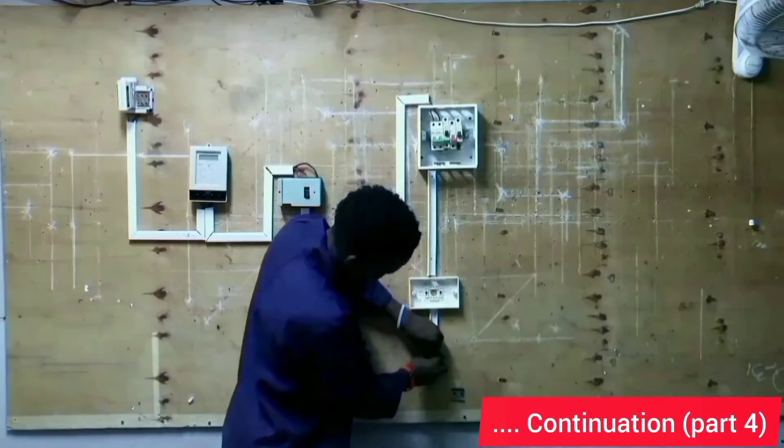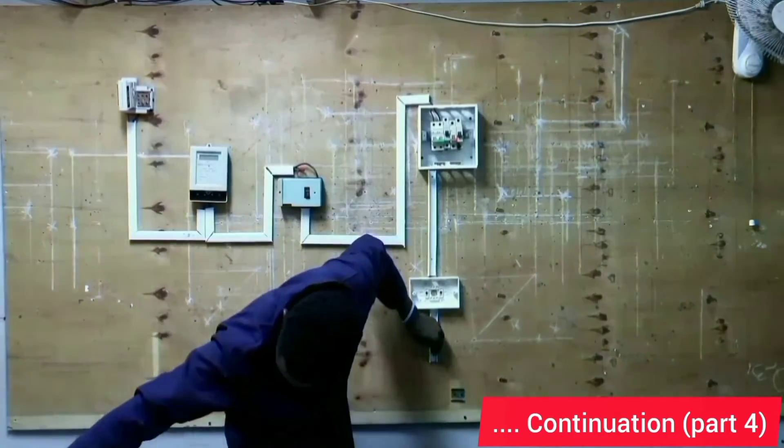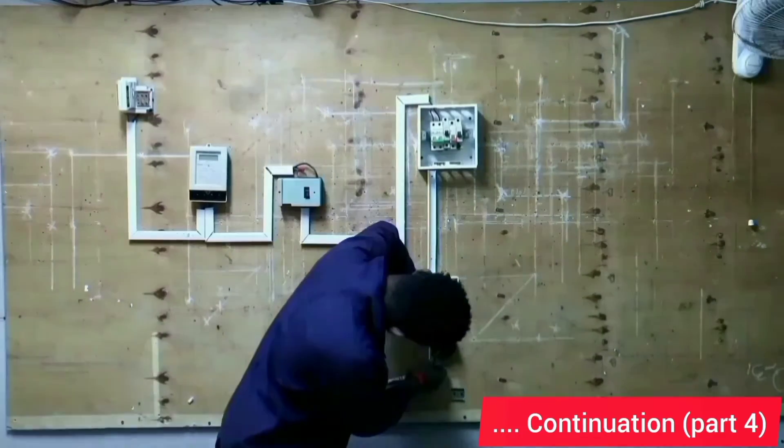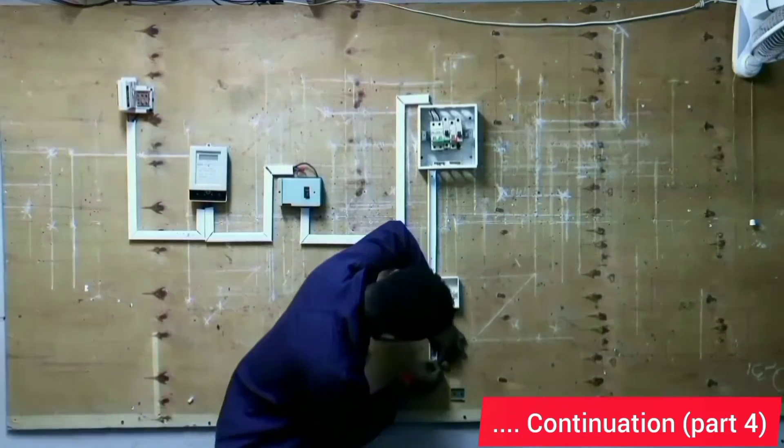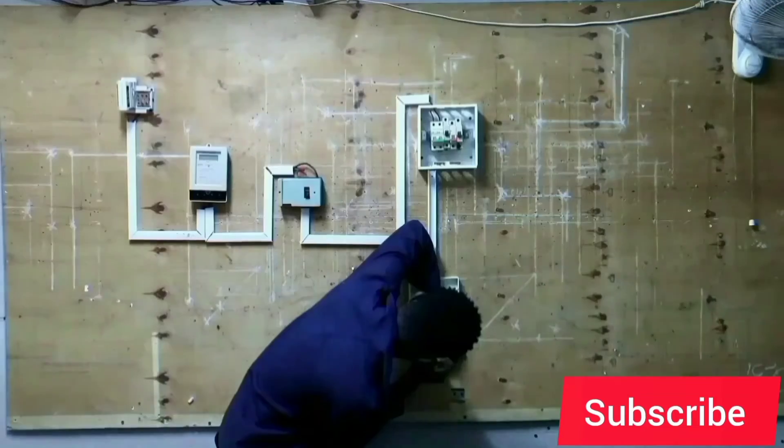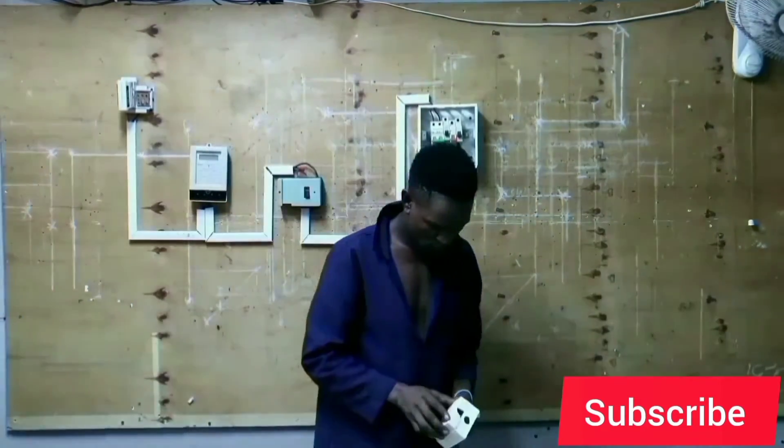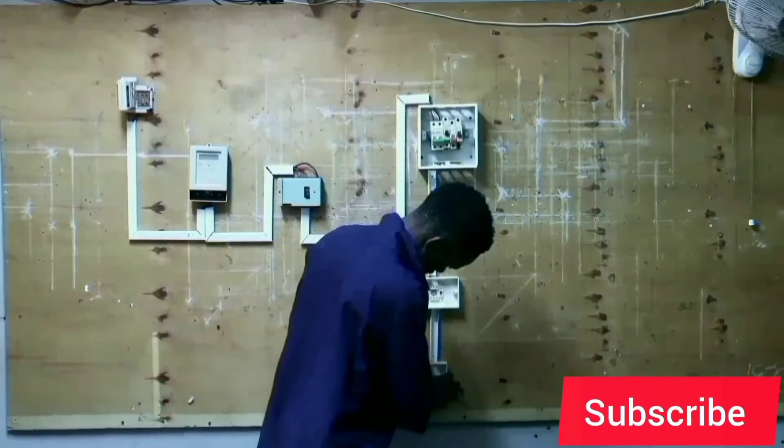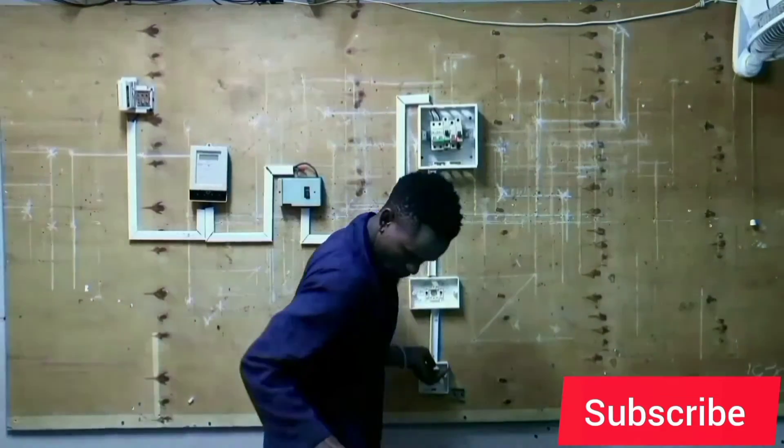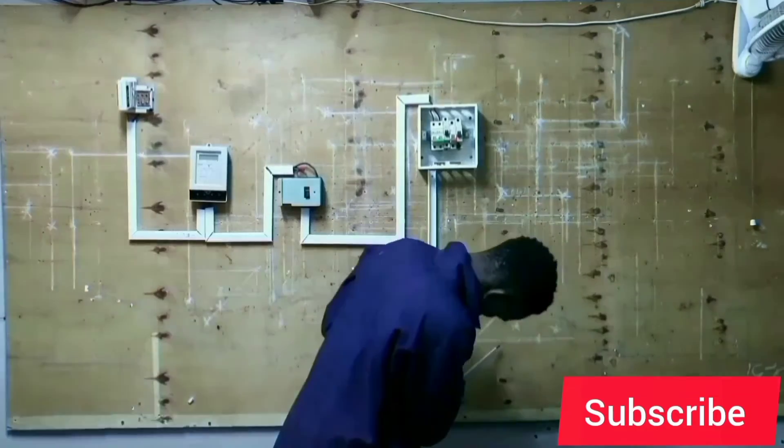We connect the cooker control unit from a 32 amp MCB using a cable of 4.0 mm². This cooker control unit incorporates a cooker control unit switch and a cooker socket outlet. The switch acts as an isolator for on-load isolation and also provides means of switching.